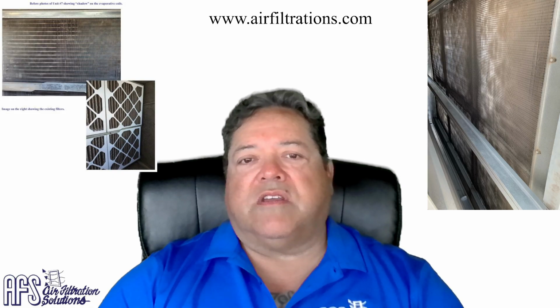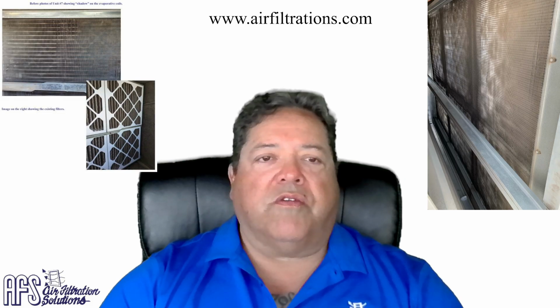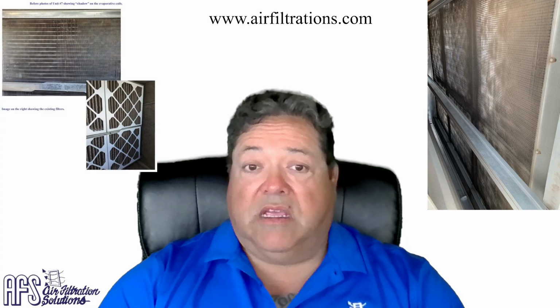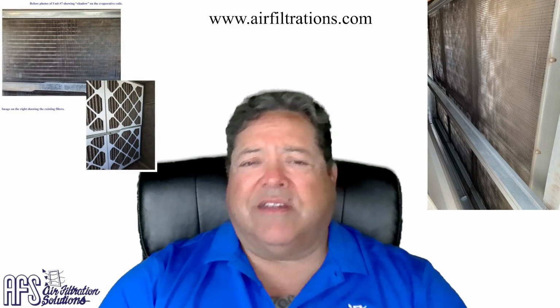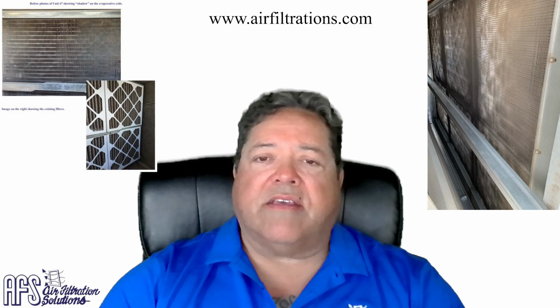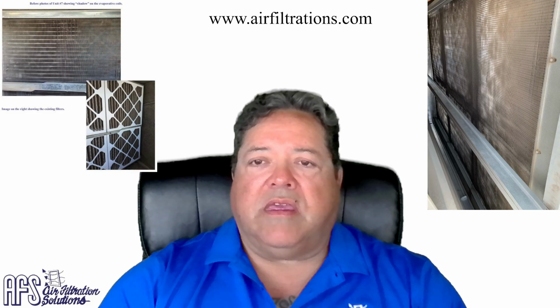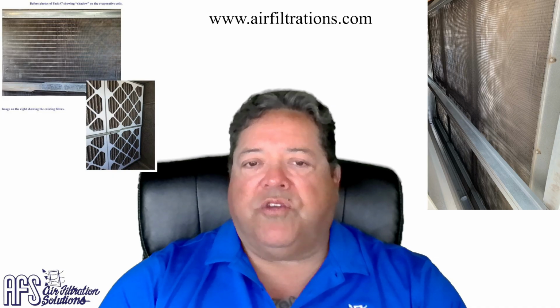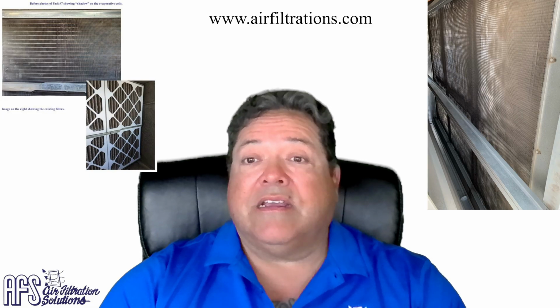So these are pictures that I've come across here on LinkedIn's newsfeed and shared with you. These are photos of mechanical contractors providing their services, which is cleaning these coils and putting new filters in place, along with some other tasks. But right here, you're seeing the incompetence of traditional cardboard filters. They're not going to keep your vital mechanical components like evaporative coils clean.